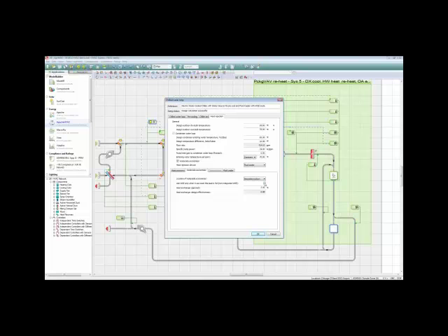Fundamental, yes. The difference is that, as I mentioned earlier, the water side economizer is using the same cooling tower as is being used otherwise to reject heat from the chiller condenser. And therefore, there's a question of whether you want it to be an integrated water side economizer, which means that when it cannot meet the full load, as long as it can still do something useful, the chiller set will turn on, and the water side economizer operation will continue as long as it can actually make colder water than it's receiving.